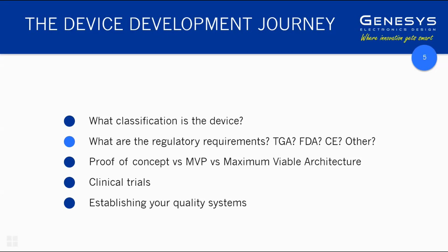Because generally speaking, what developers do is they choose one jurisdiction in which to get their device registered and compliant with the appropriate regulatory standards. In Australia, that's the Therapeutic Goods Administration, and some companies may choose to get it certified in Australia, and then that certification is mutually recognised by other countries such as the US, which is the Federal Drug Administration, CE mark in Europe. Jeff, any comments on what the trend is these days?